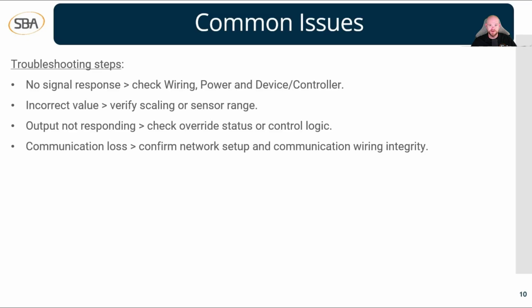The biggest one here, communication losses. Communication losses happen all the time in BASs, guys, so be prepared for this one. But two common things to check when we're troubleshooting a communication loss is to confirm the network setup, make sure that your network setup is correct, and then go through and check your communication wiring. Make sure that it is integral. Make sure everything is correct with your wiring.